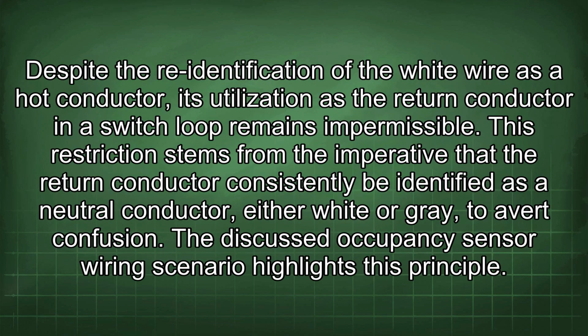Despite the re-identification of the white wire as a hot conductor, its utilization as the return conductor in the switch loop remains impermissible. This restriction stems from the imperative that the return conductor consistently be identified as a neutral conductor, either white or gray, to avert confusion.